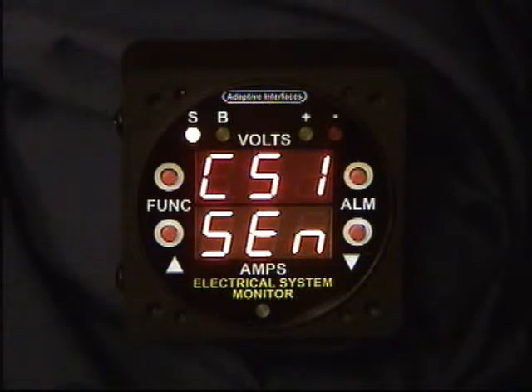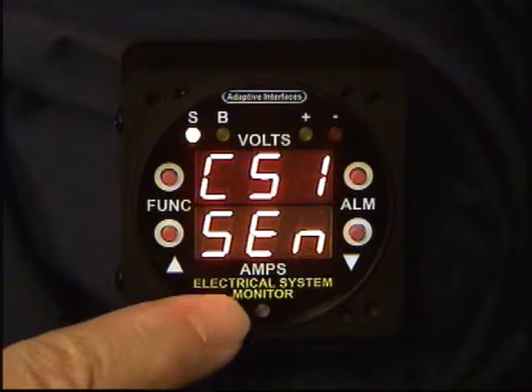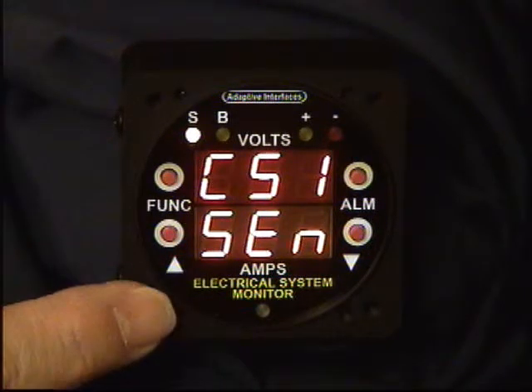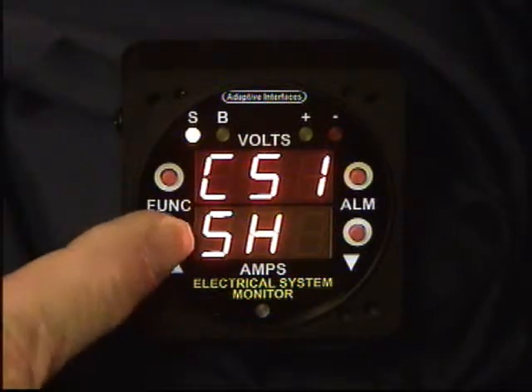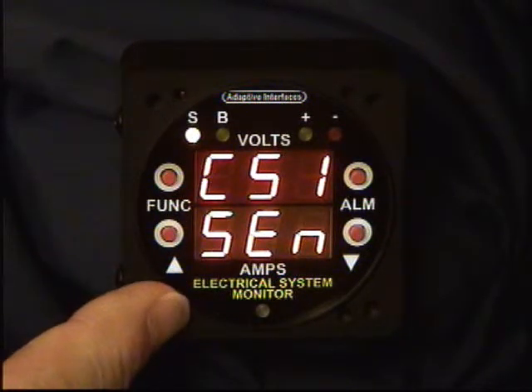Next function is the selection of the type of current sensor to be used for the first current sensor, or the system current sensor. The instrument is designed to work with a standard 50 millivolt shunt. The shunt values can be anywhere from 10 to 100 amps. It's also designed to be used with a series of Hall effect current sensors. The current sensors available with the instrument are 25 amps, 50 amps, and 100 amps. Right now, a Hall effect current sensor has been selected for current sensor number 1. That can be changed to a current shunt if you wish. We'll just leave it as a sensor for right now.